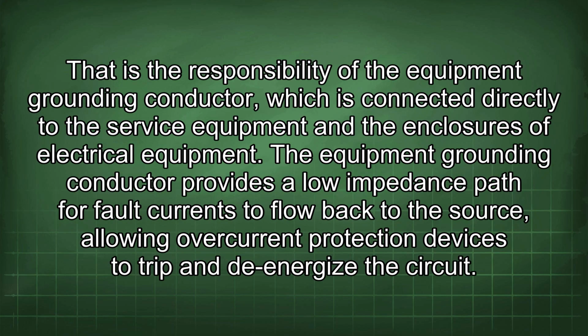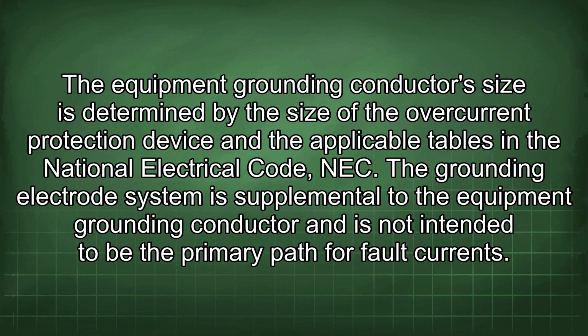It is essential to understand that the grounding electrode system is not designed to carry large fault currents. That is the responsibility of the equipment grounding conductor, which is connected directly to the service equipment and the enclosures of electrical equipment. The equipment grounding conductor provides a low impedance path for fault currents to flow back to the source, allowing overcurrent protection devices to trip and de-energize the circuit. The equipment grounding conductor's size is determined by the size of the overcurrent protection device and the applicable tables in the National Electrical Code, NEC.